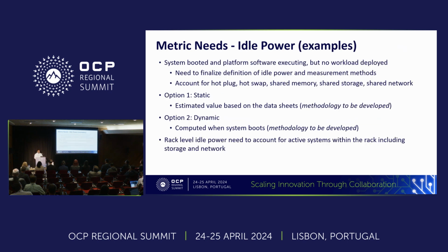Then when you're looking at idle power, this is one of the areas where, if you look at the systems, you may have 10 percent or even more of power consumed by the idle power of the processors, memory subsystems and all the devices sitting there. You could potentially put a static value depending on how you compute it. Or when you are testing the system, you can measure how much idle power is consumed before you start putting any workloads on the system.